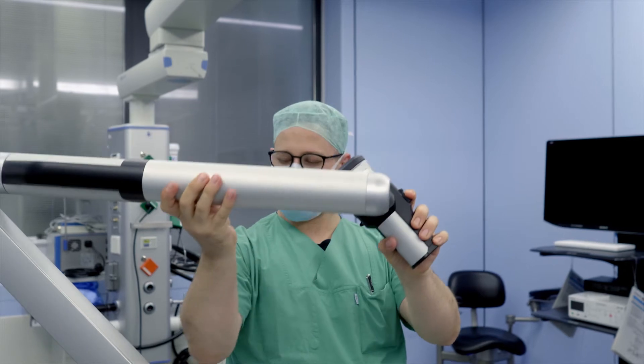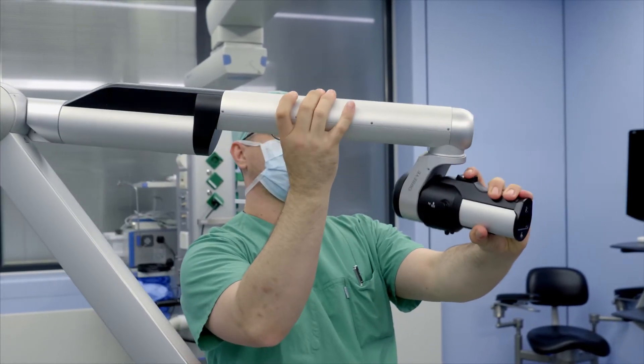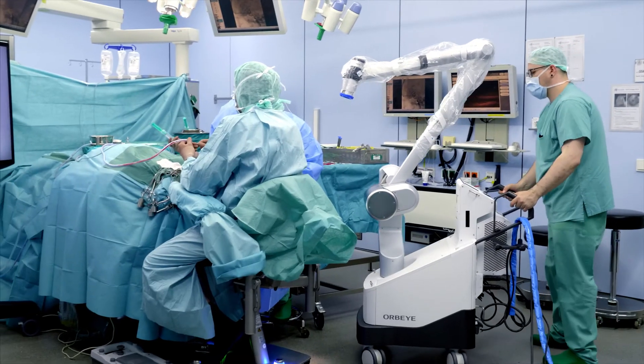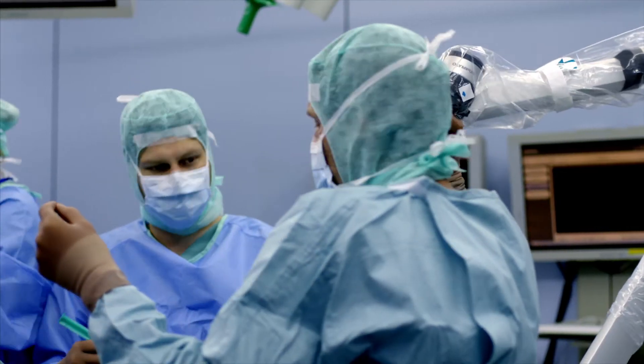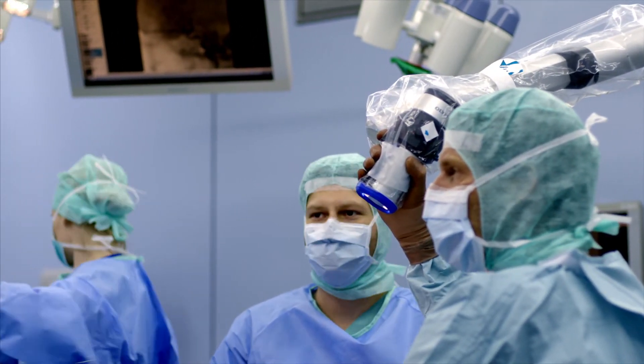The Orbeye system offers a flexible arm that enables the camera to be positioned in any direction, while allowing the surgeon to maintain a recommended ergonomic posture without needing to tilt the operating table or change their own position. Instead, only the camera position is adjusted. There is no need to balance, painstakingly adjust, or calibrate the light sources.